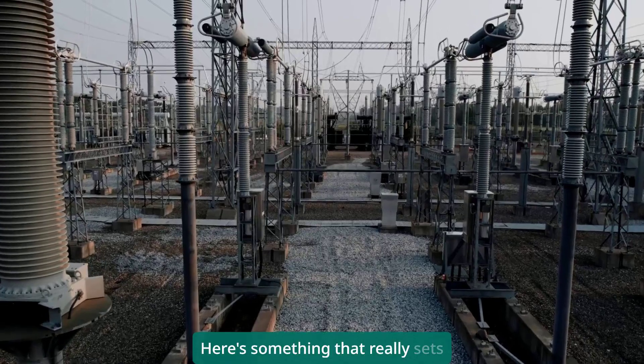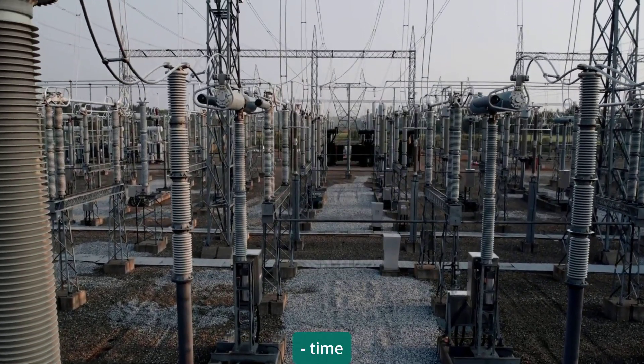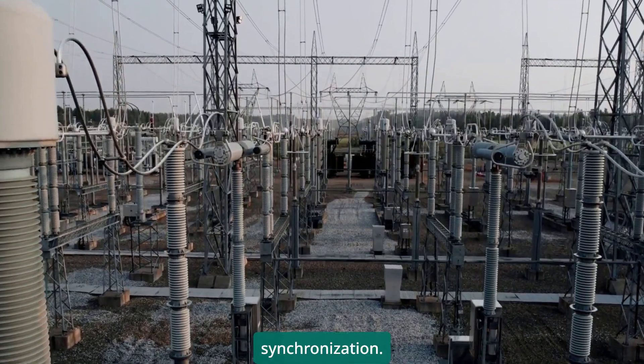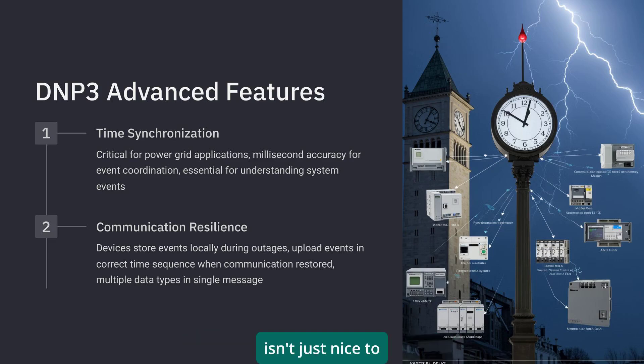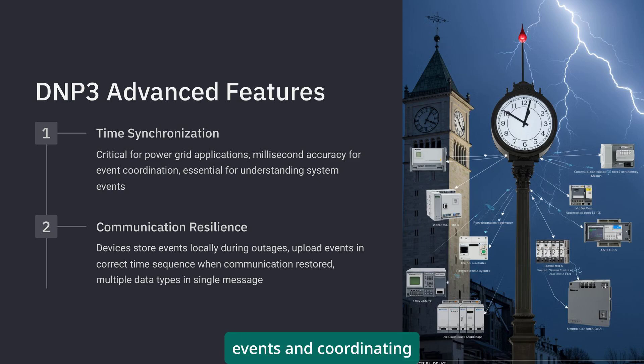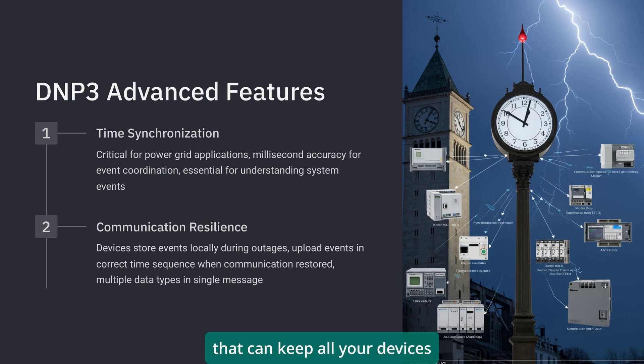Here's something that really sets DNP3 apart: time synchronization. In the power grid, knowing exactly when something happened isn't just nice to have — it's critical for understanding system events and coordinating protection schemes. DNP3 has built-in time sync capabilities that can keep all your devices synchronized to within milliseconds.